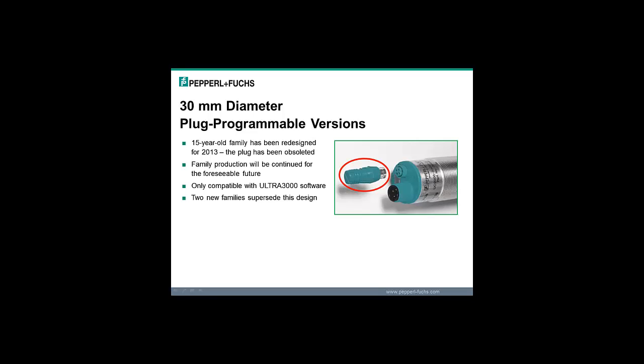Okay, this is important to note that our 30 millimeter diameter plug programmable versions, if you're familiar with those, they have a socket in the back and a small plug that you could rotate, and you learn maybe one switch point and the end of your switch points to make a window, or the 4 milliamp and 20 milliamp components of an analog span. That family P&F has offered for probably over 15 years, and it is going to be obsoleted in favor of 2 new families. But it's not going to go away very quick, and I'm sure we'll keep it around for the next 3-5 years because there's such an installed base of it, and it's been a very popular series.